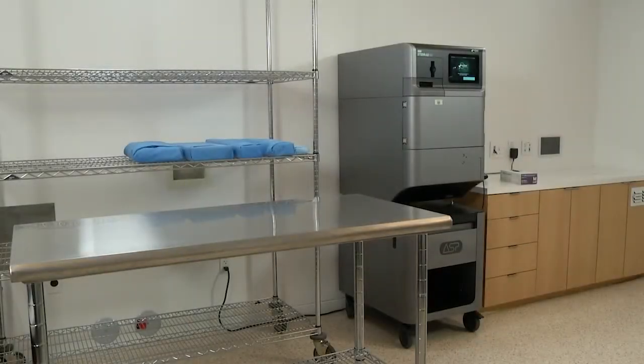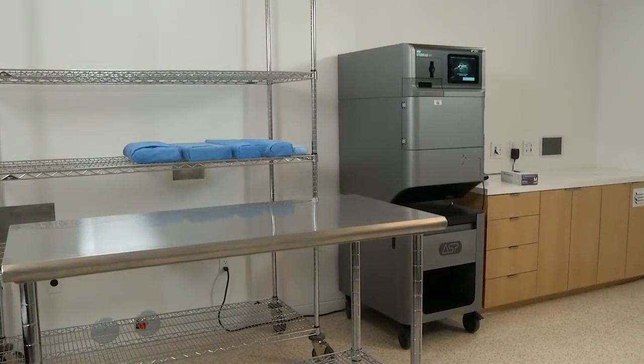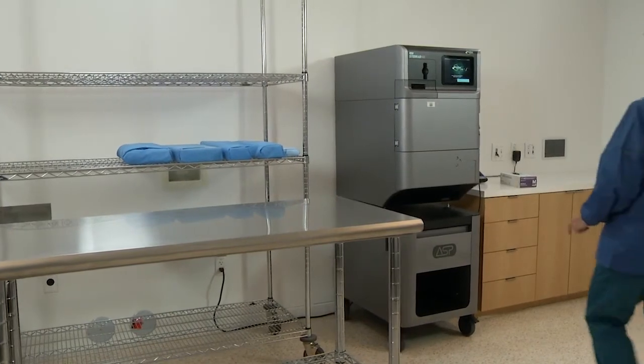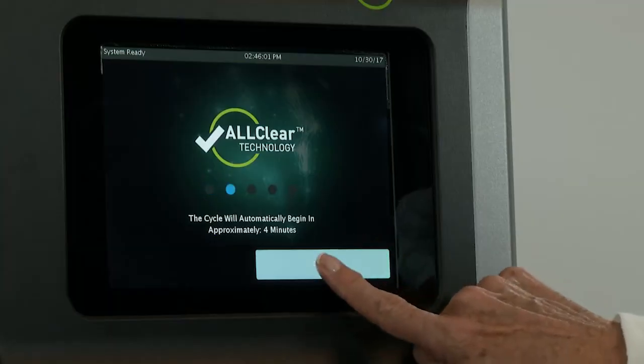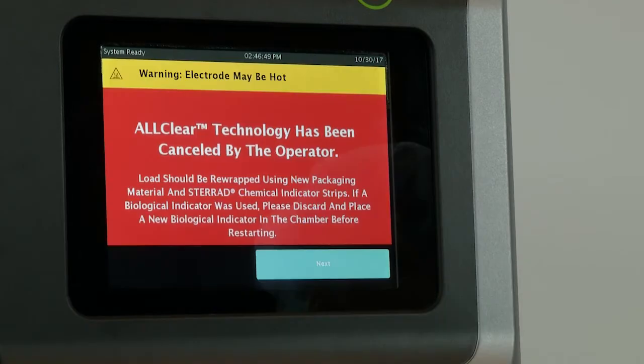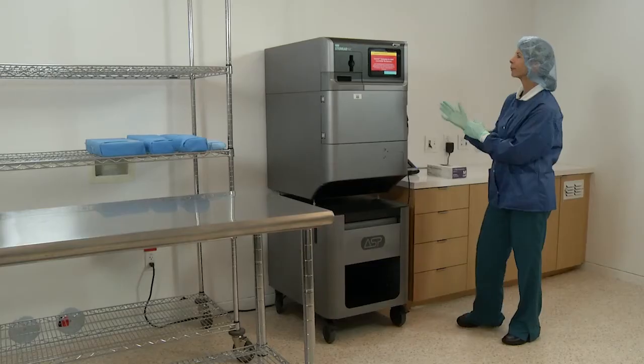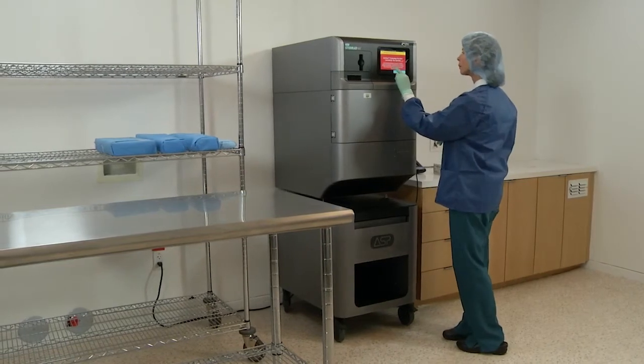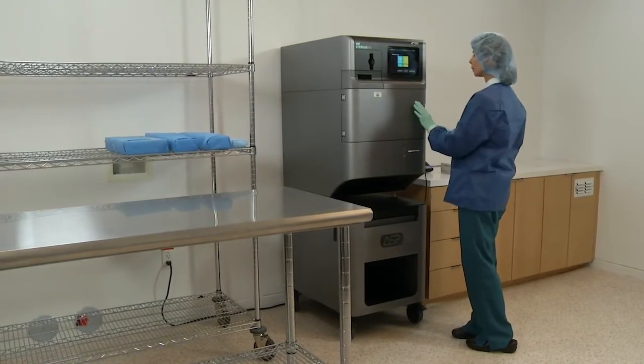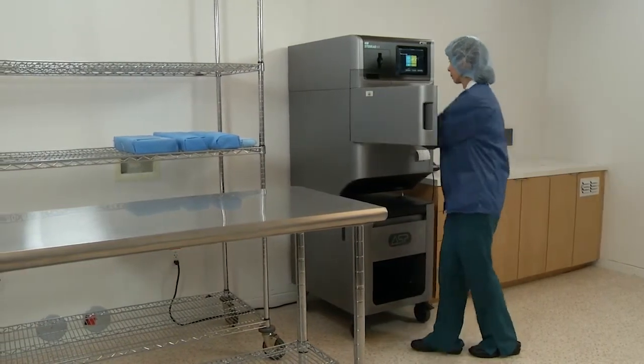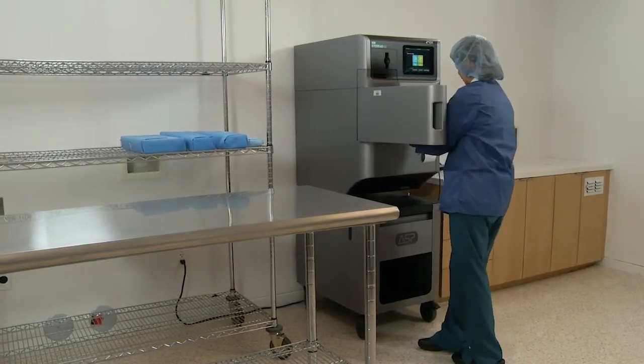There may be occasions when it is necessary to cancel a cycle before it is completed. To cancel a cycle, simply touch the Cancel Cycle button. The screen will display a confirmation message. Because hydrogen peroxide may be present, always wear chemical-resistant latex, PVC vinyl, or nitrile gloves when removing items from the sterilizer following a canceled cycle.